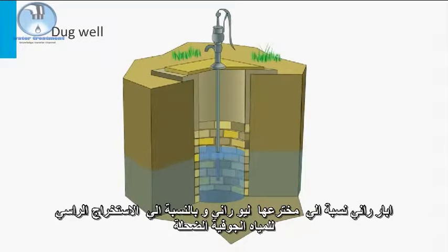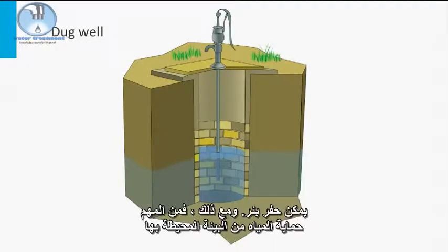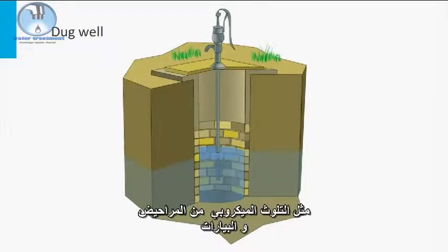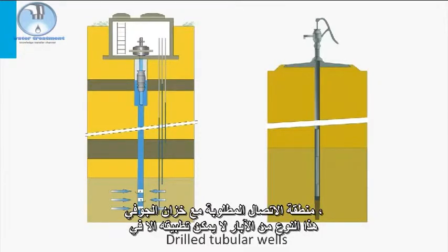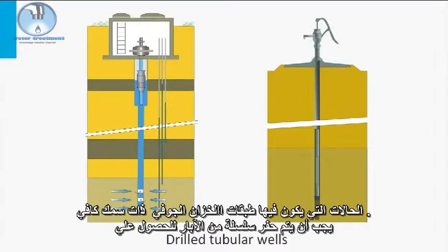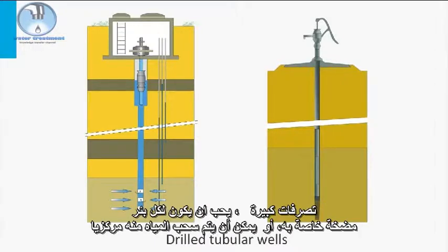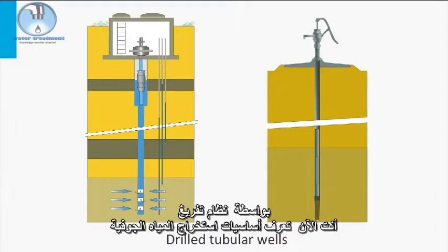For the vertical abstraction of shallow groundwater, a dug well can be used. However, it is important to protect the water from its surroundings, such as faecal contamination by latrines or livestock. The most widespread method for vertical abstraction is drilled tubular wells. These can only be applied where aquifers have enough thickness. A series of wells must be constructed for larger capacities, and every well can be supplied with its own pump or centrally drained with a vacuum system.